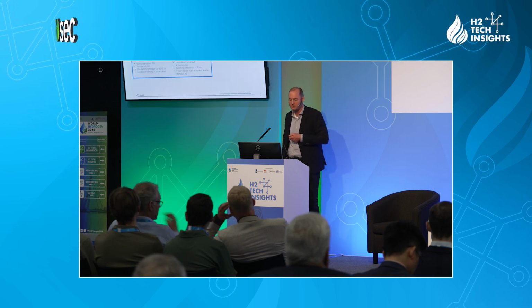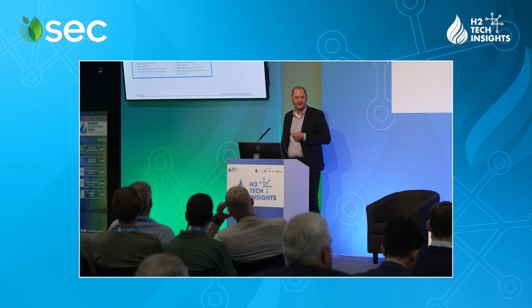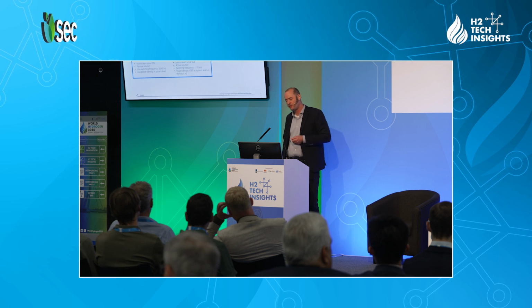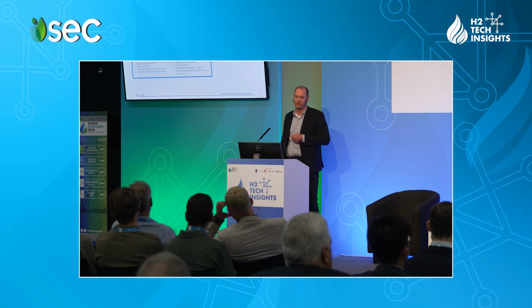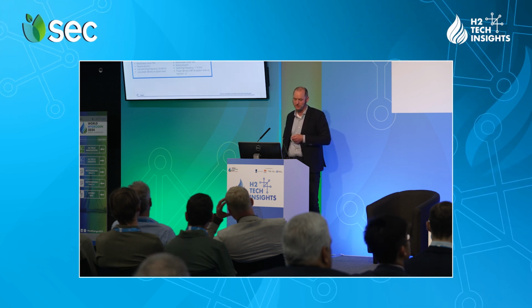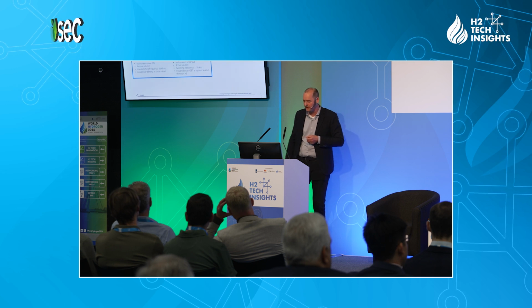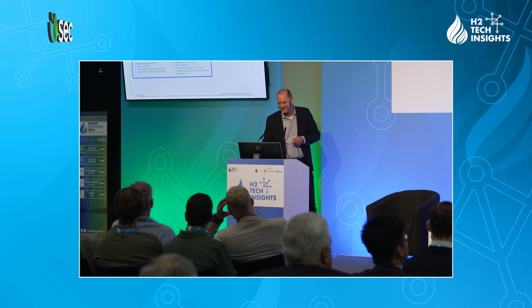So IGBTs are a big improvement already. They're mainstream since the 90s. They are offering an active solution. Switching frequency is already higher than the grid by an order of magnitude. And the power density is also already improved compared to thyristors by about a factor of 2.